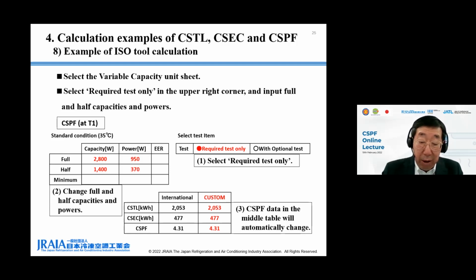Next, as an example, full capacity 2,800, full power 950, half capacity 1,400, and half power 370 in watts are entered in the standard condition 35°C table at the upper left corner. Then CSTL 2053 and CSEC 477 in kilowatt hour and CSPF 4.31 are automatically shown in both the international and custom rows of the middle table. Because this example is in ISO T1 condition, the data for international and custom rows are the same.